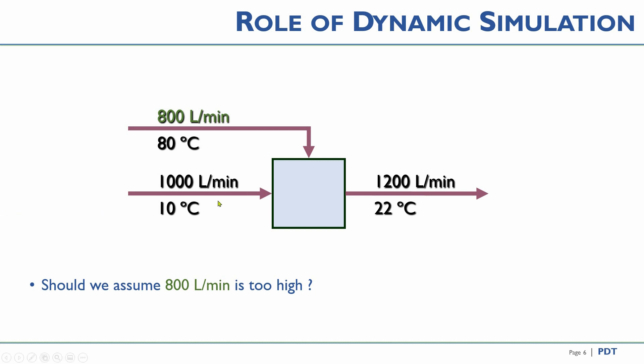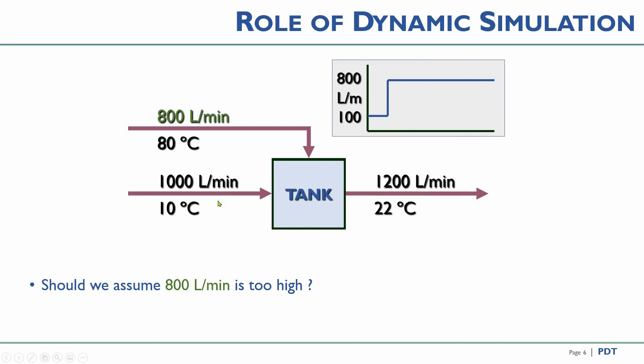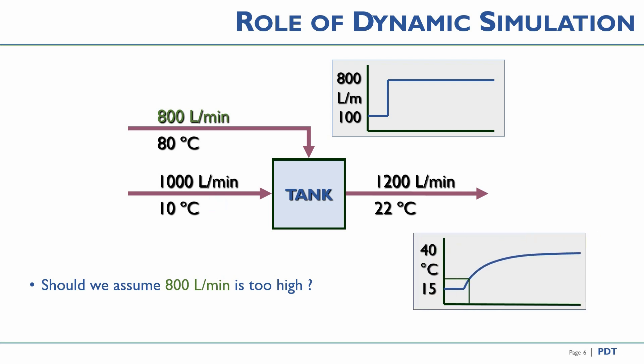However, if we have a bit more information — that the process is a tank and the inlet flow was 100 a few seconds ago and now it is 800 — this starts to explain some things. The outlet flow is on level control and is working its way up from 1100 to 1800, and the temperature is logically on its way up from 15 degrees to near 40. Everything is actually perfect with these measurements, and these would fool other systems which do not use a dynamic process simulation that understands transient behavior.